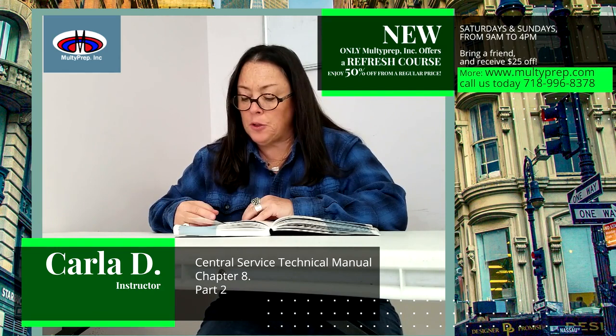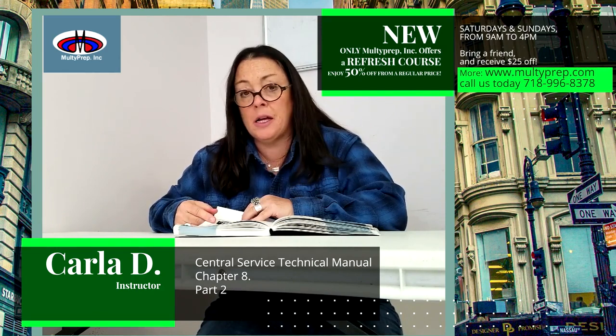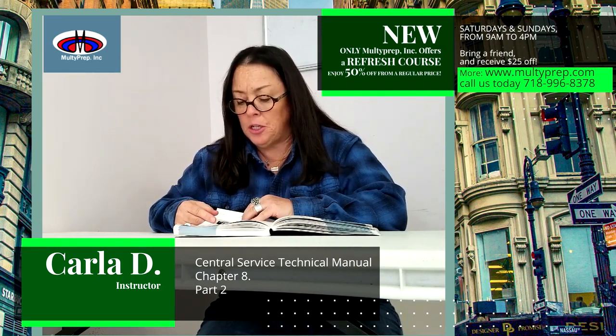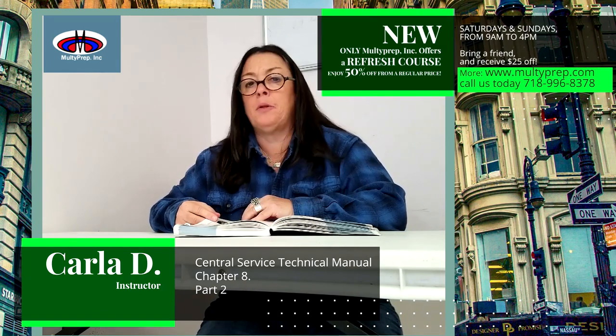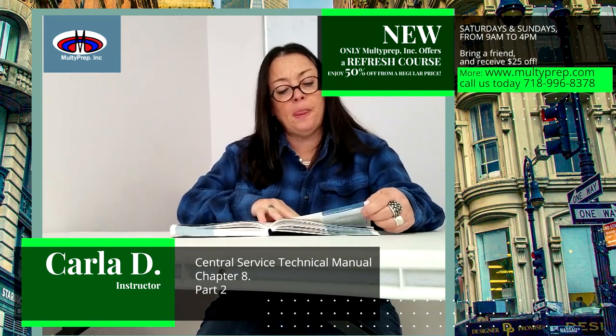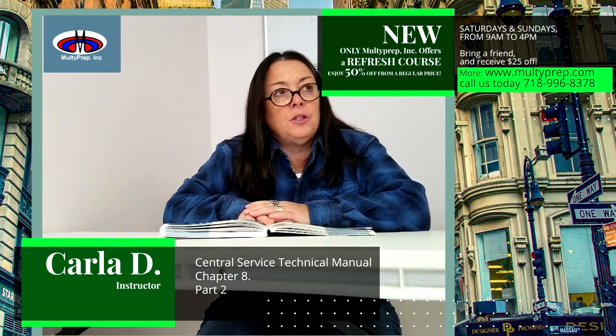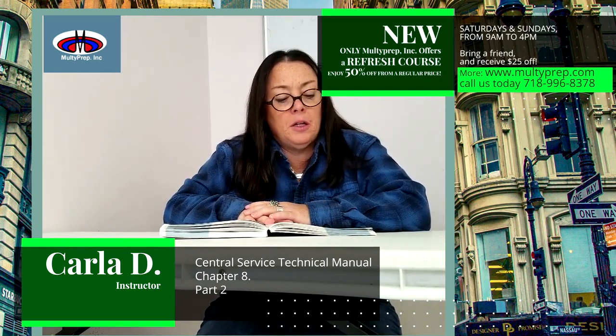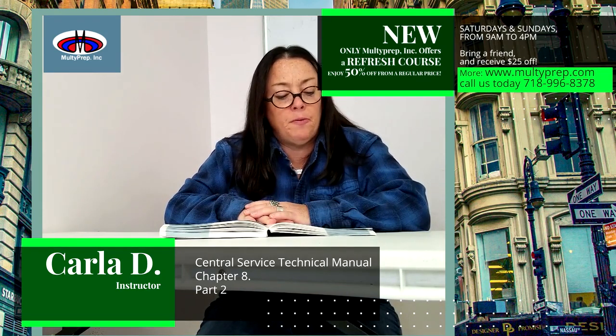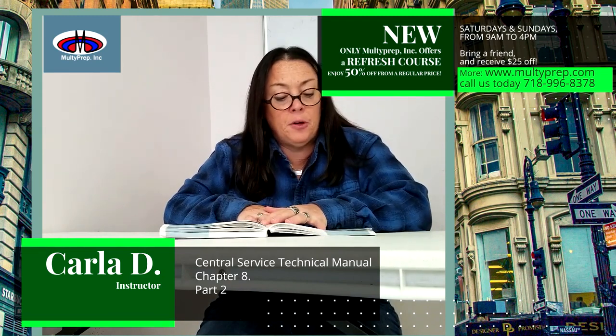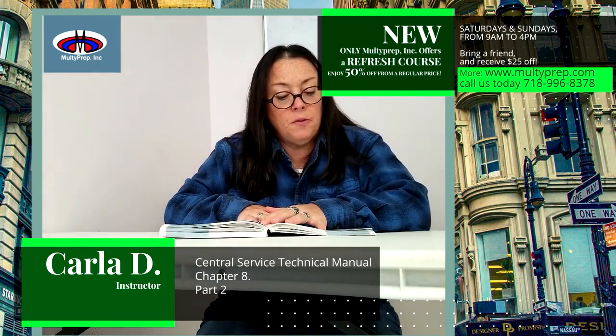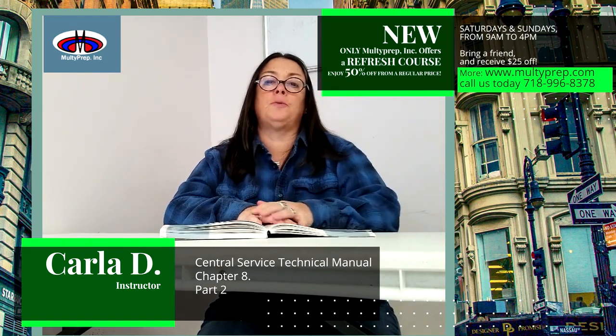Note: be sure to follow the facility's specific protocols for processing eye instruments. Pay attention to detail and do not take shortcuts at any step in the process. There are thousands of instruments on the market, and cleaning each one requires specific knowledge. Instruments designed to perform the same function but made by different manufacturers may need different cleaning processes. Consult the device manufacturer for special considerations and to determine if these devices can withstand automated washers.